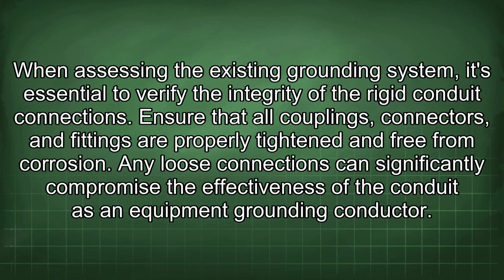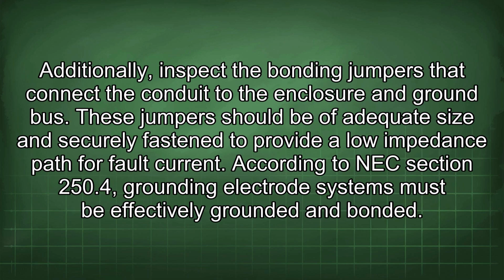When assessing the existing grounding system, it's essential to verify the integrity of the rigid conduit connections. Ensure that all couplings, connectors, and fittings are properly tightened and free from corrosion. Any loose connections can significantly compromise the effectiveness of the conduit as an equipment grounding conductor. Additionally, inspect the bonding jumpers that connect the conduit to the enclosure and ground bus. These jumpers should be of adequate size and securely fastened to provide a low impedance path for fault current.